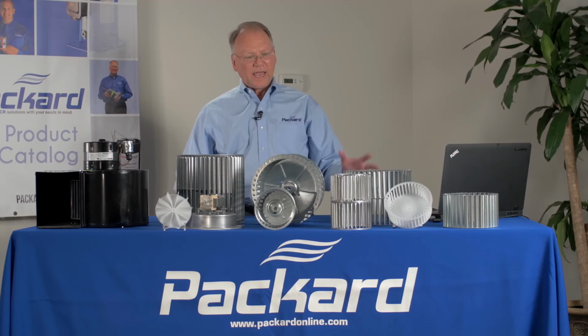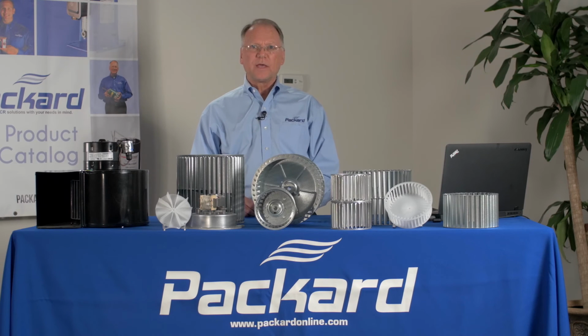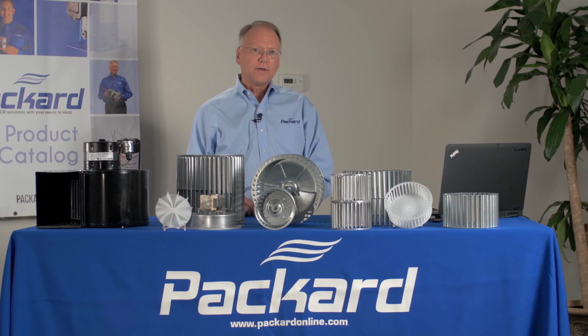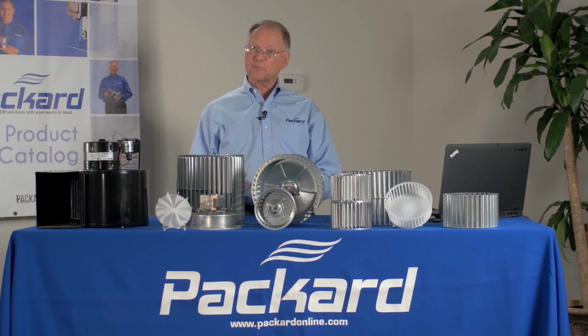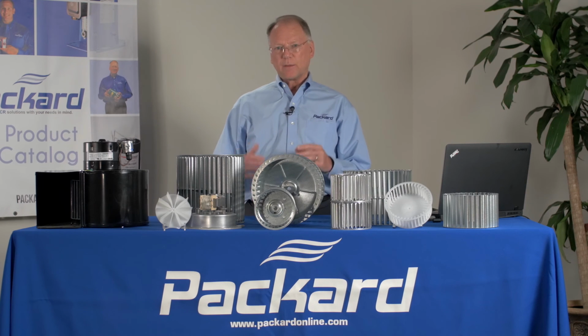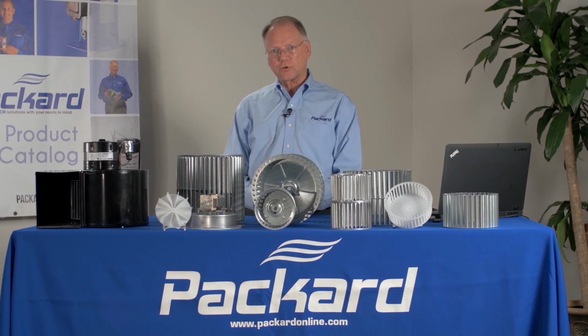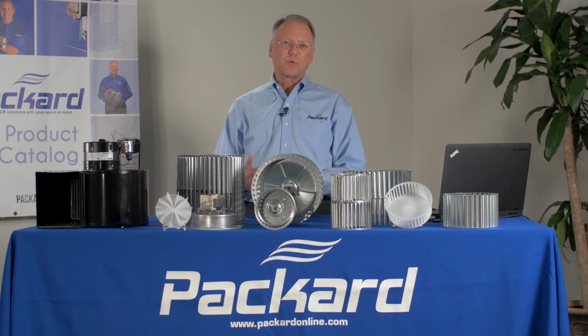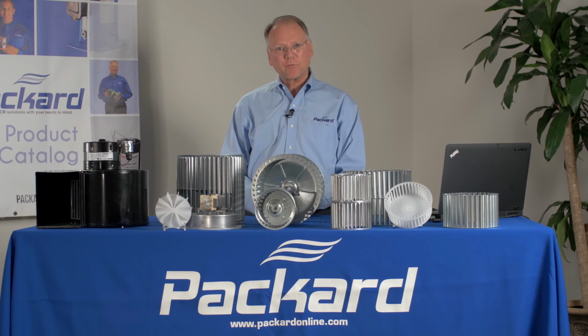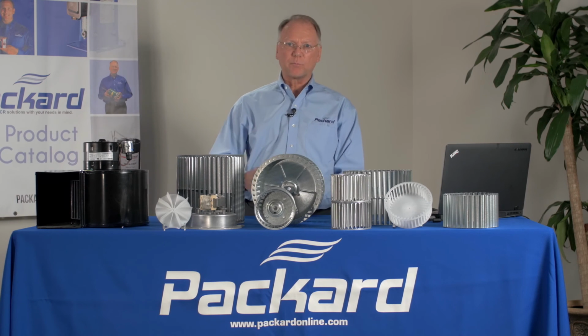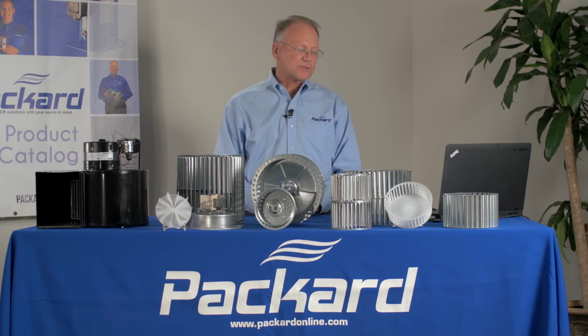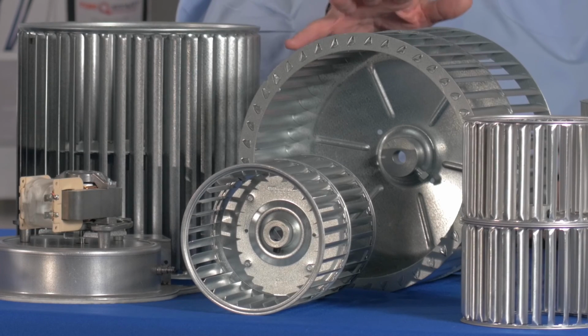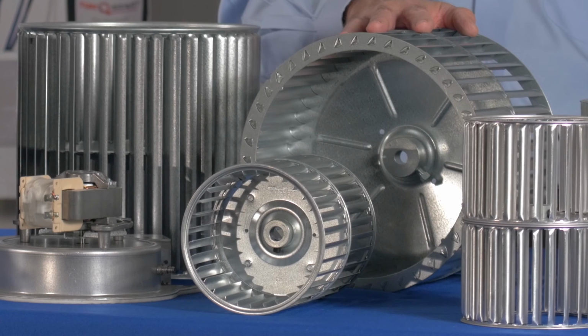After you've selected a wheel and installed the blower wheel into the housing, it's important to make certain that the amps are okay on that particular motor. When checking the amps, be certain that the static pressure is appropriate, giving you the proper performance of that wheel. In future videos, we'll be covering the effect of static pressure on the blower wheel to provide deeper insight into that. You want to make sure that the air delivery is proper in the system.